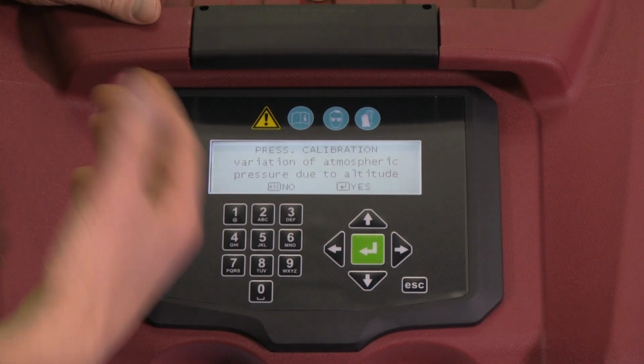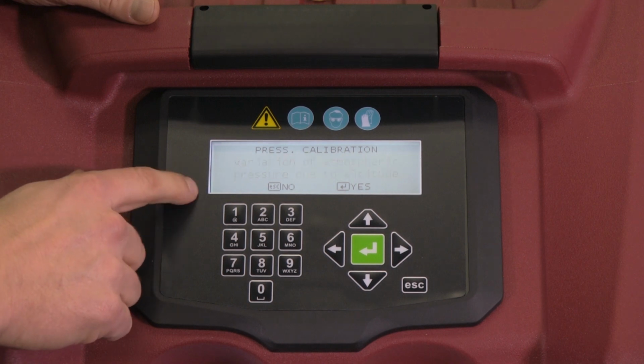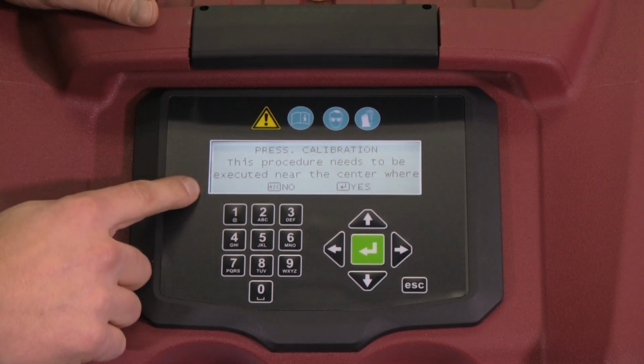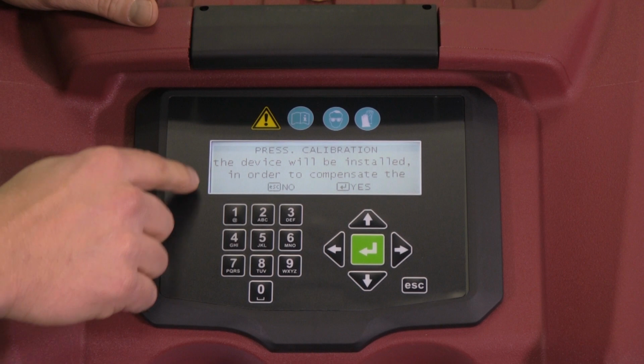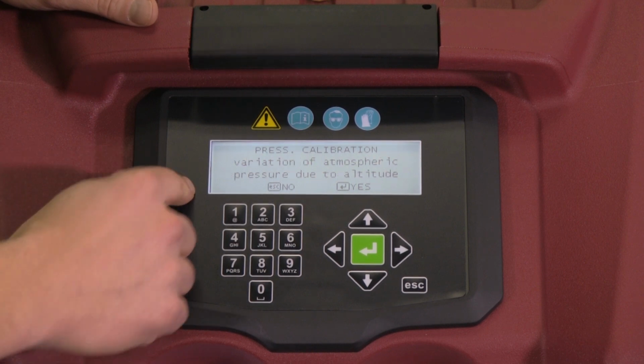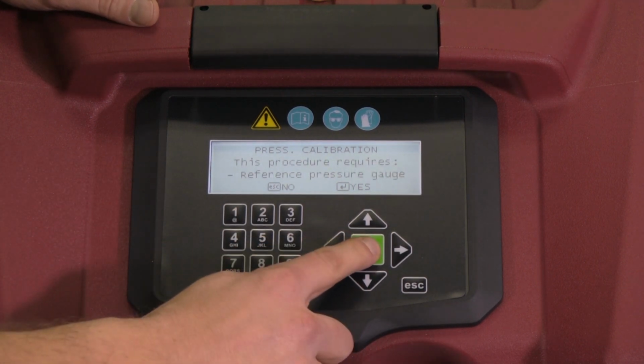Now it's going to tell us that this needs to be performed near where the device is going to be installed. This is because these units work at atmospheric pressure, and so we want to zero it to the location that the machine's being used.